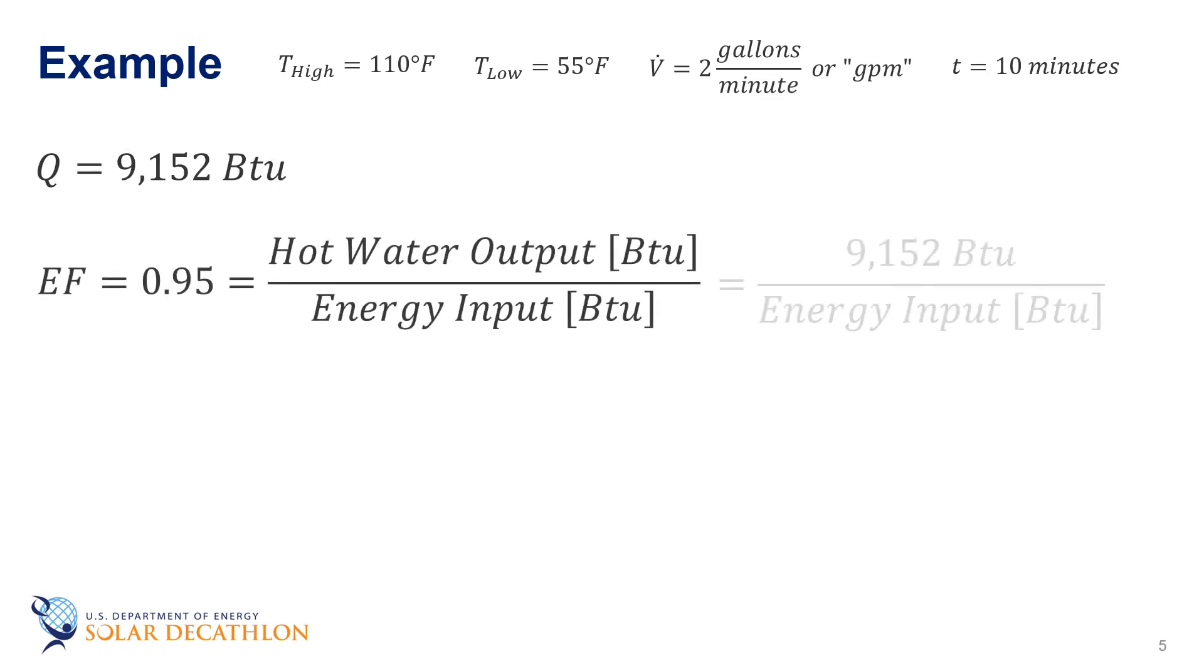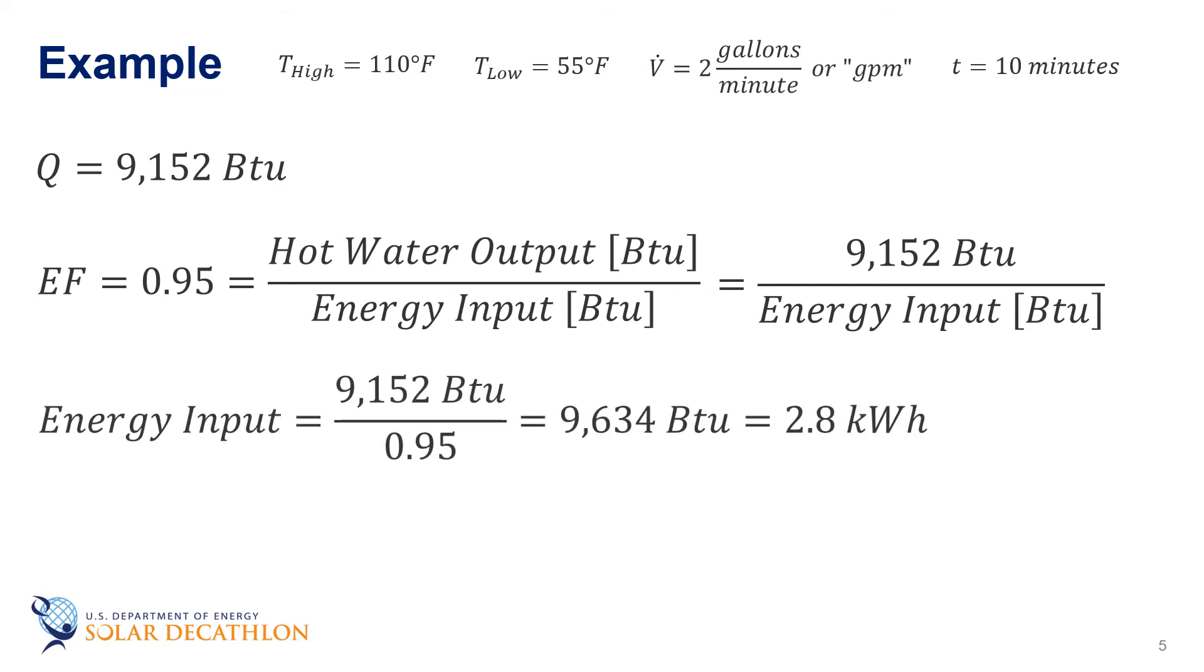If the energy factor of the hot water heater is 0.95, which is typical for an electric resistance unit, then the energy required is 9,634 BTUs or about 2.8 kilowatt hours. If, as an example, electricity is 15 cents a kilowatt hour, then the cost for the shower is about 42 cents.